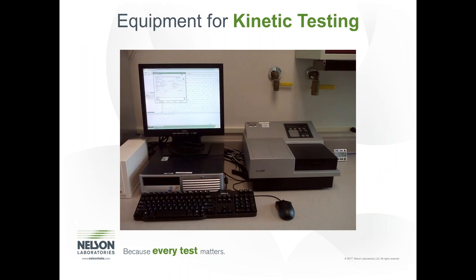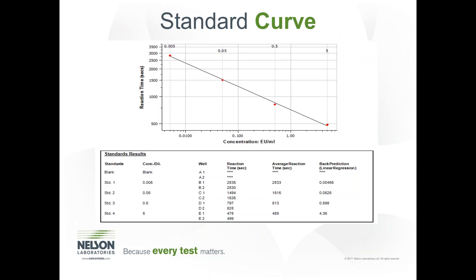Here is an image of some equipment used for endotoxin testing. This is what the standard curve would look like — you can see the reaction times of the different controls used, in this case from 5 EUs per ml down to 0.005 EUs per ml. This slide shows what a kinetic test would look like in real time. You can see in row E that the strongest control has started reacting, and we can actually notify customers before we get an actual result. Endotoxin testing is often quite time dependent.